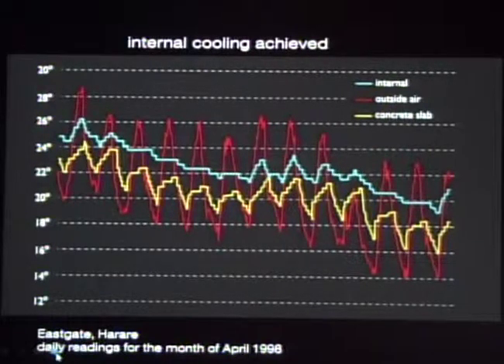And that's the result. The red line is the day and night diurnal shift, each zigzag is a day and a night. The yellow line is the concrete slab temperature, and the blue line is the average internal temperature. You can see how the concrete modifies the internal temperature from the diurnal shift, giving about 4 degrees of cooling, as we designed originally, from a diurnal shift of 12 degrees. It's purely by changing the air flow rates: about 10 air changes during the night, switching to about 2 air changes during the day, which is enough for ventilation. You can then spread the cooling effect over the whole day, particularly in the afternoon, and you can vary that timing very simply.